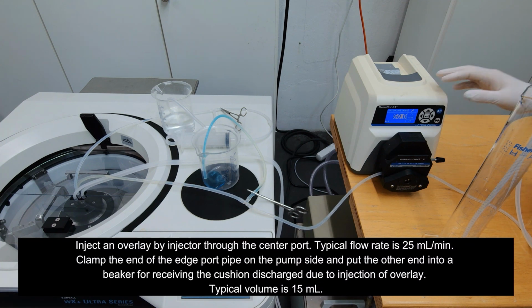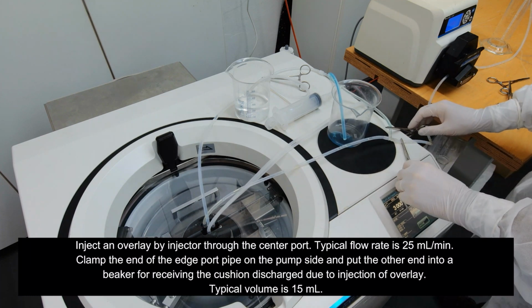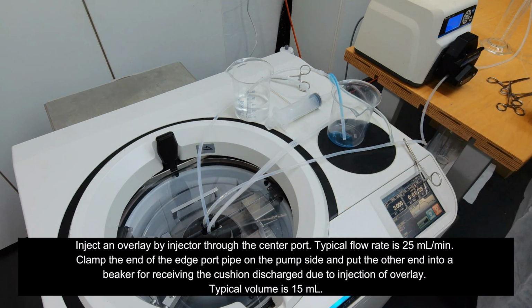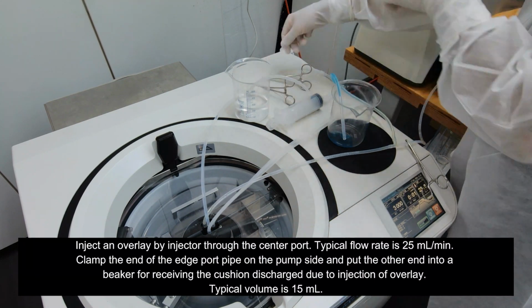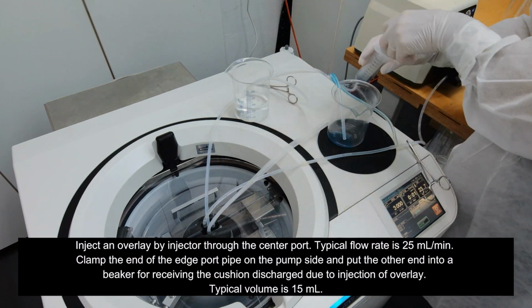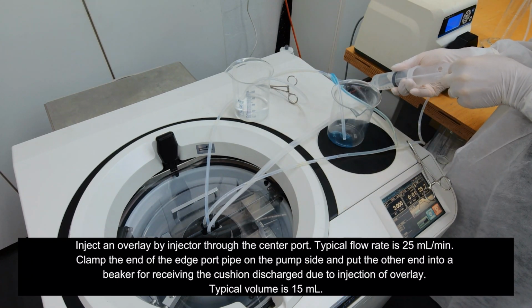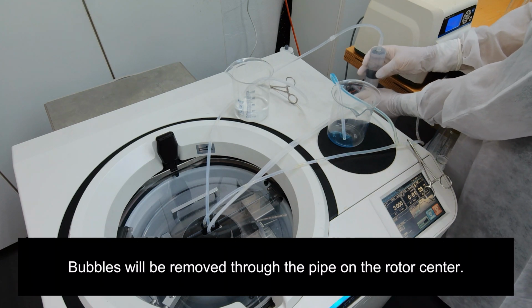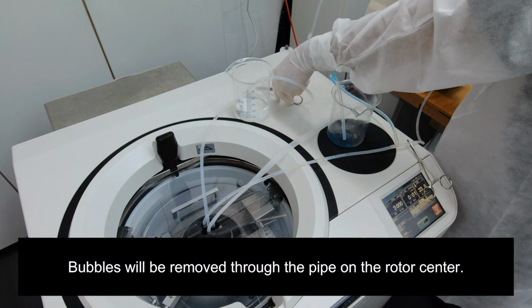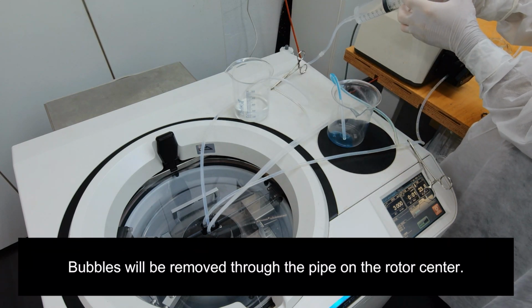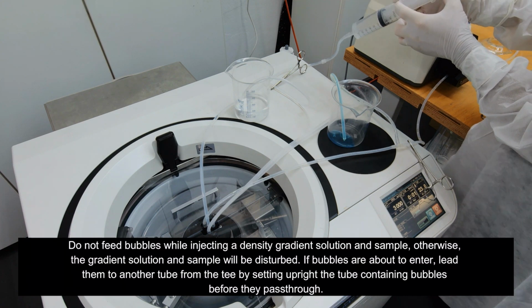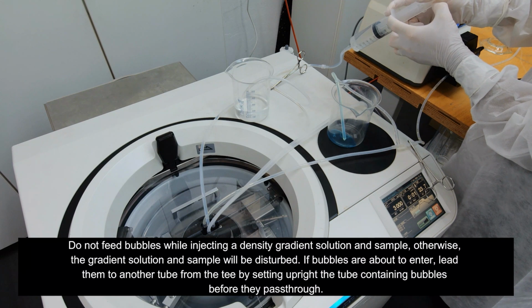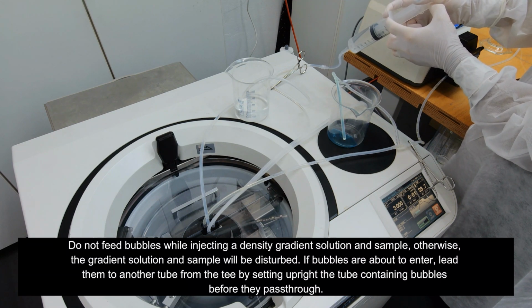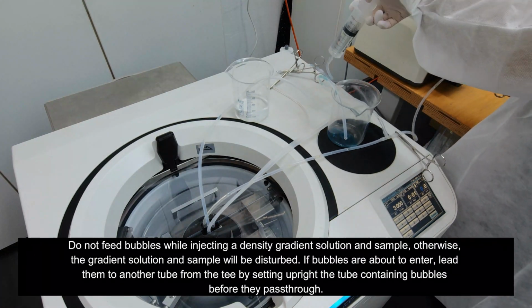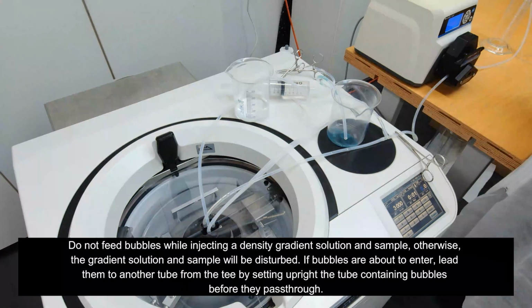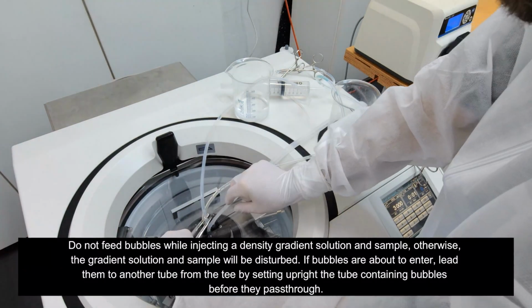Inject an overlay by injector through the center port. Typical flow rate is 25 milliliters per minute. Clamp the end of the edge port pipe on the pump side and put the other end into a beaker for receiving the cushion discharge due to injection of overlay. Typical volume is 15 milliliters. Bubbles will be removed through the pipe on the rotor center. Do not feed bubbles while injecting a density gradient solution and sample, otherwise the gradient solution and sample will be disturbed. If bubbles are about to enter, lead them to another tube from the T by setting upright the tube containing bubbles before they pass through.